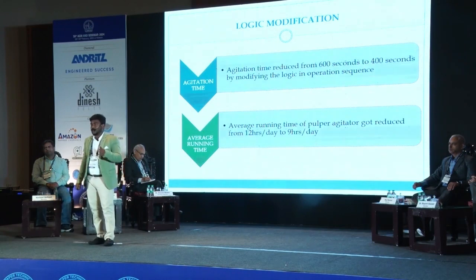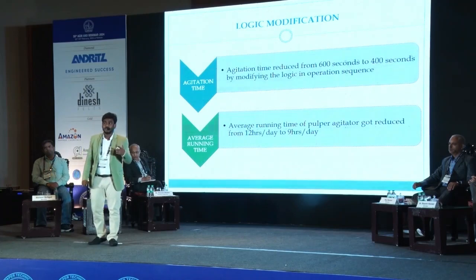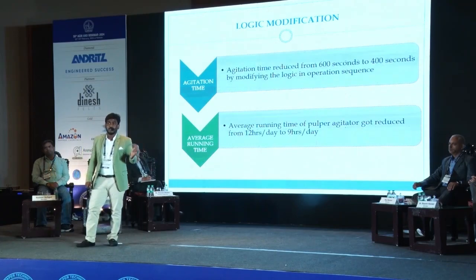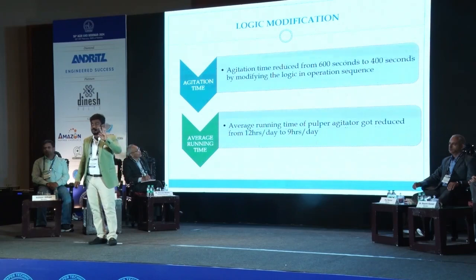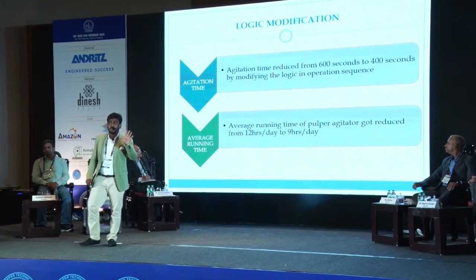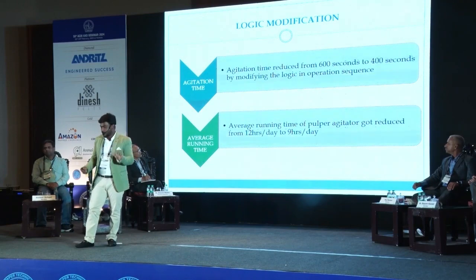The average running time of the real pulper was 12 hours per day, and for the pre-dryer section pulper it was 7 hours per day. By reducing 200 seconds of agitation time in the logic, the average running time has come down to 9 hours per day for the real pulper and 4 hours per day for the pre-dryer section pulper, saving us 3 hours per day of agitator running. That is 3 hours of 315 kilowatt motor running saved per day.